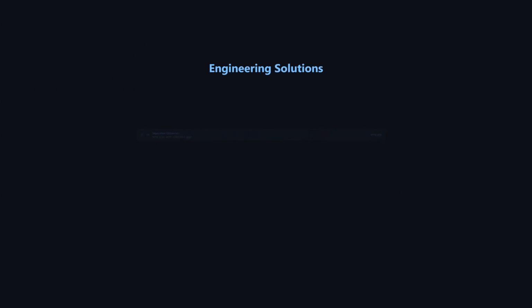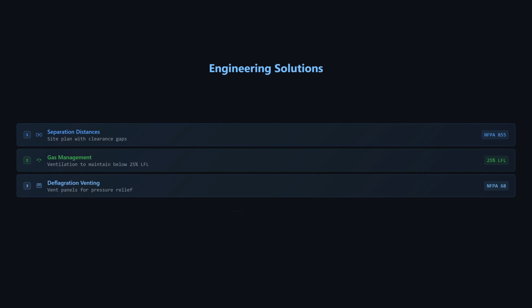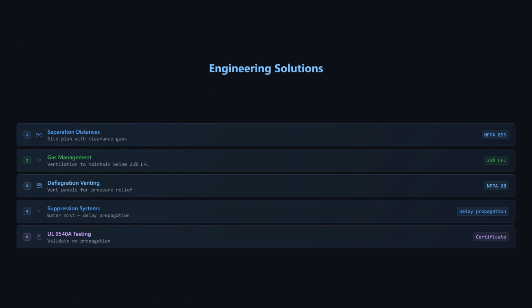A properly engineered BESS installation requires layered protection. Start with separation. NFPA 855 specifies minimum distances between battery enclosures and between BESS and occupied buildings. The 2026 edition introduces thermal runaway prevention and propagation requirements for the first time. For gas management, engineered ventilation maintains concentrations below 25% of the lower flammable limit. Deflagration venting per NFPA 68 provides pressure relief. Suppression systems, typically water mist or clean agent, delay propagation and protect the structure, even though they can't stop thermal runaway. And critically, the UL 9540A test standard validates that a BESS design won't allow cell to cell, module to module, or unit to unit fire propagation. Every BESS installation should be tested to this standard.